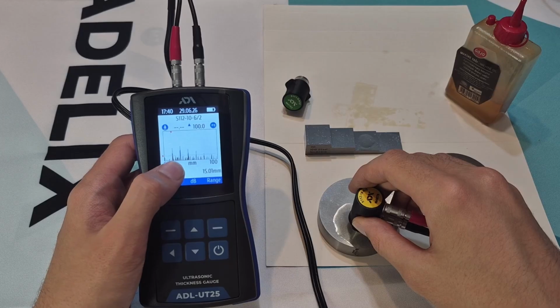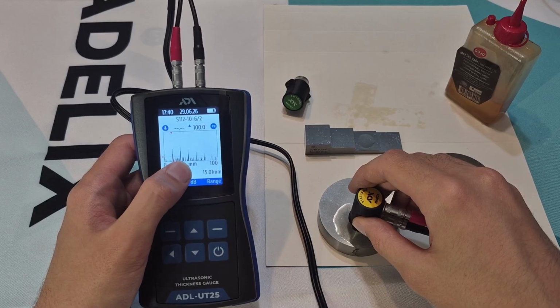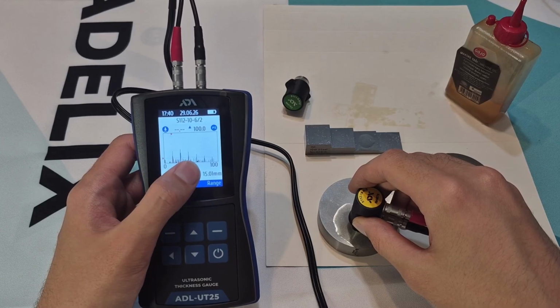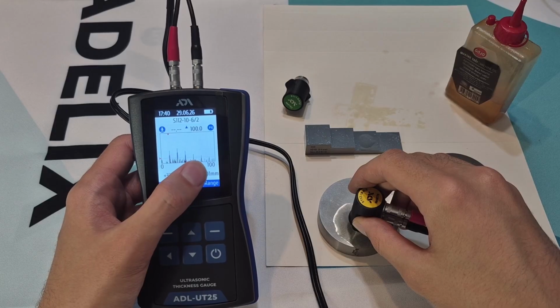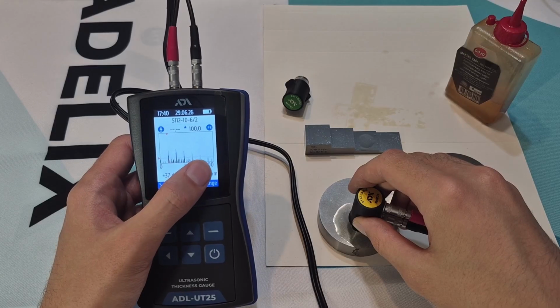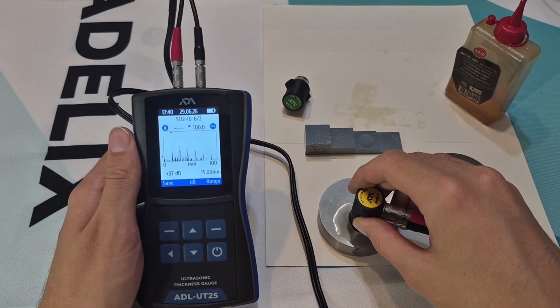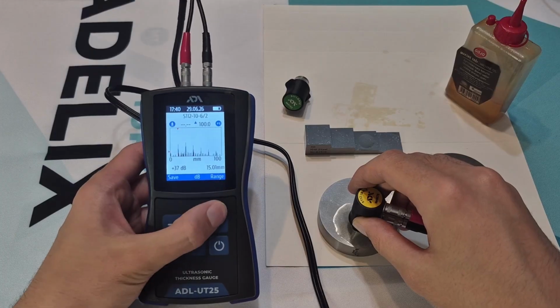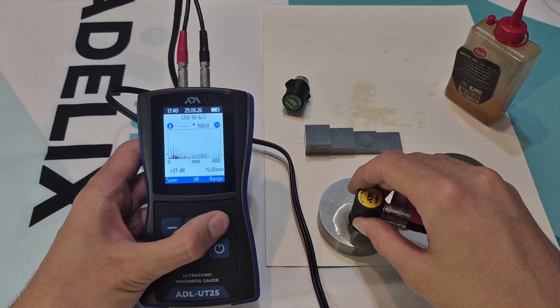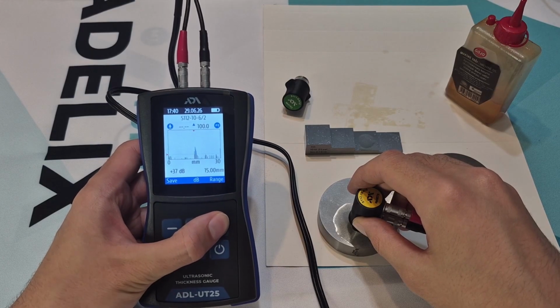If the measurement range is increased, subsequent signal reflections can be seen. For example, for a 15 mm thick sample, the values 15, 30, 45, 60, 75 and 90 mm will be displayed. For a 10 mm thick sample, 10, 20, 30 mm and so on.